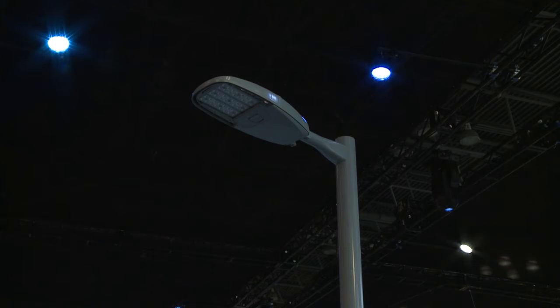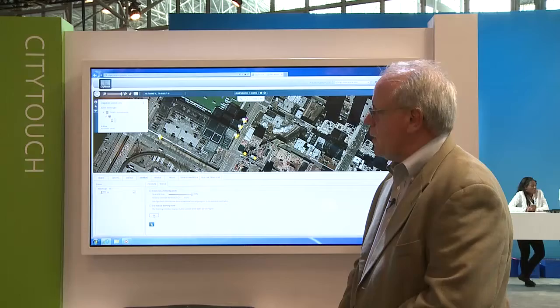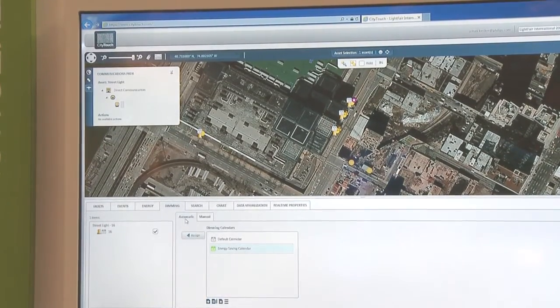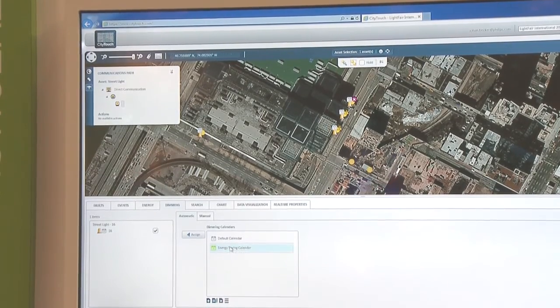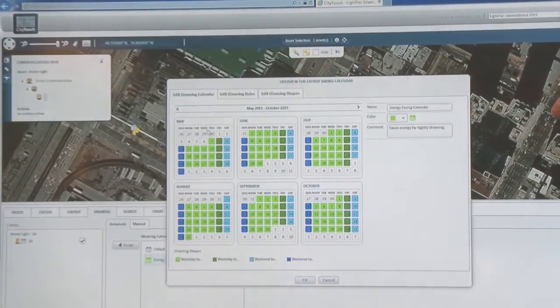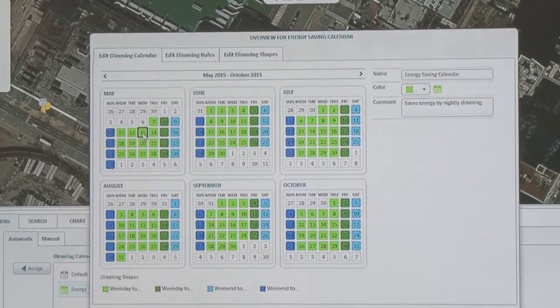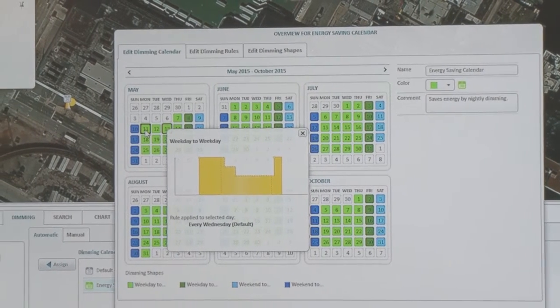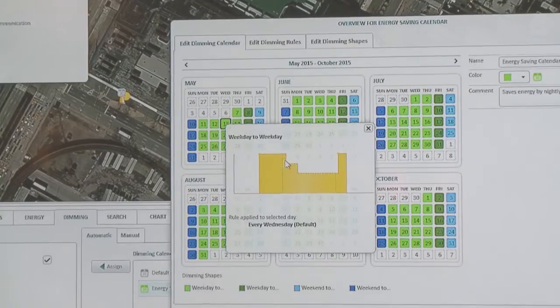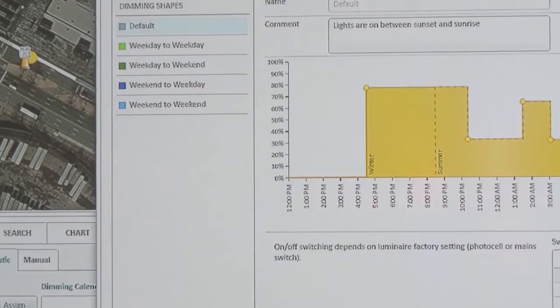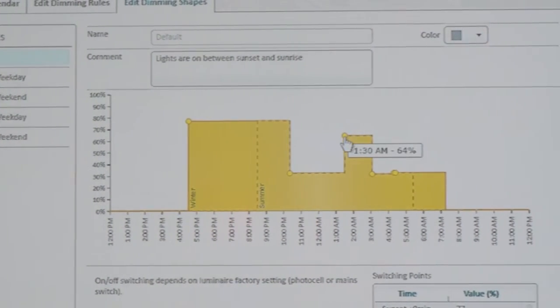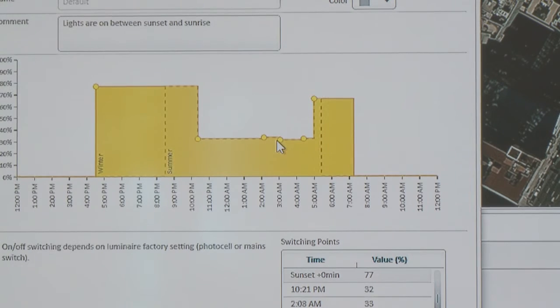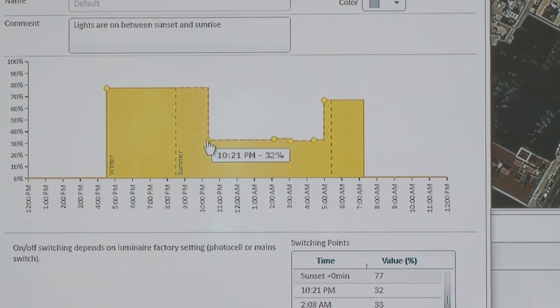This is happening in real time — the information goes over to Europe and comes back to the US through the cellular network, and the streetlight is now turned on. With this system, not only can you manually control the lights, but you can also set up individual calendars. You can set up individual dimming cycles depending on the day of the week, month of the year, or special events, and establish a nighttime dimming curve if you don't need as much illumination during off-peak hours. You can easily edit the dimming curve using the dimming editor and adjust the dimming profile to whatever you might want on any given day or night.